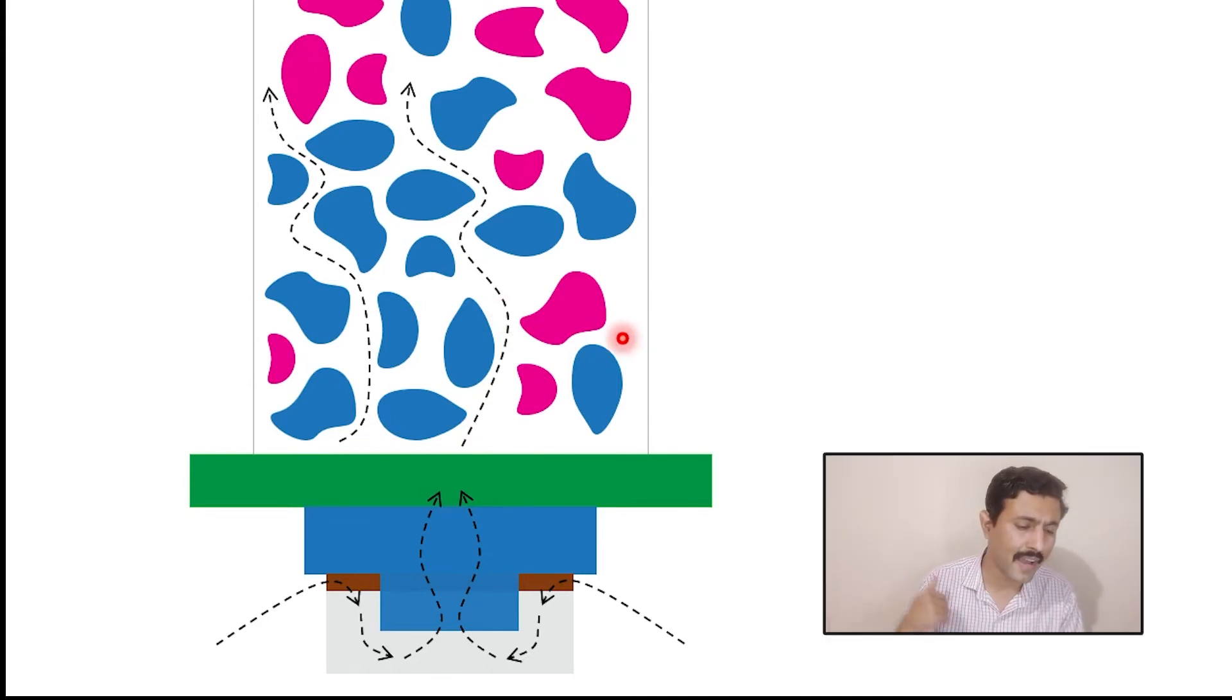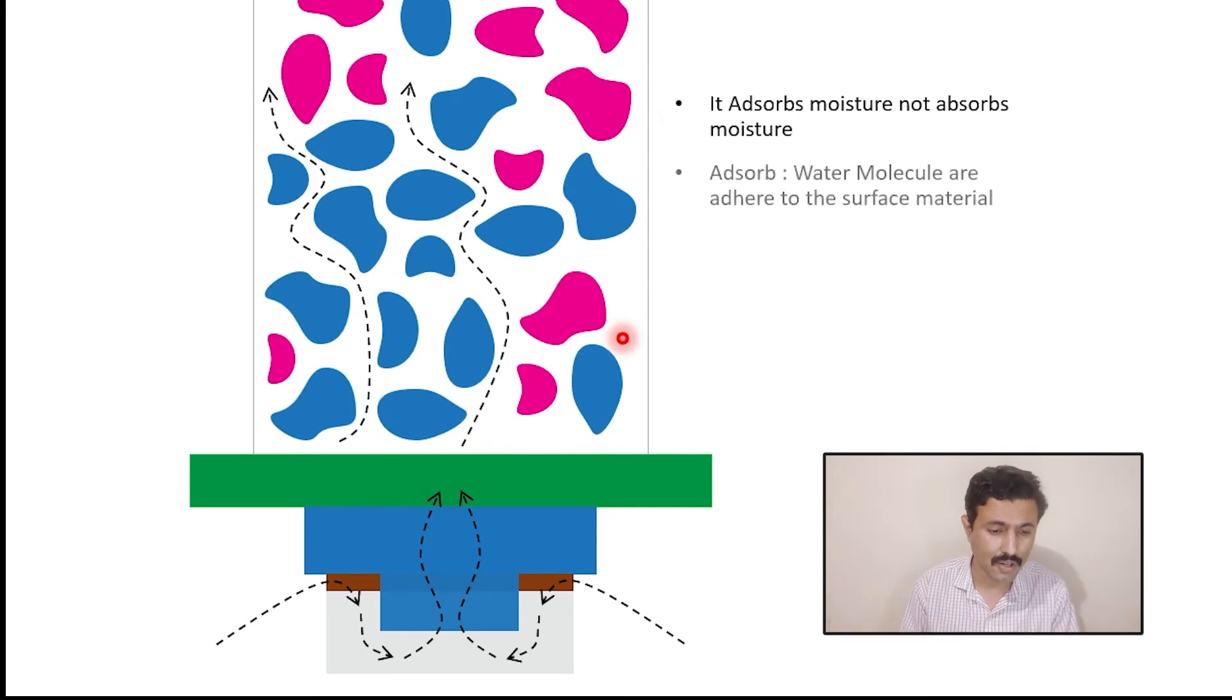Then, followed by this filter, air enters to this cylinder. When air flows through this cylinder, there is silica gel. The moist air flows through the silica gel and this silica gel adsorbs the moisture from the air. Remember that it adsorbs the moisture, not absorbs the moisture. Basically, the meaning of adsorb is the water molecules in the moist air get adhered to the surface material.